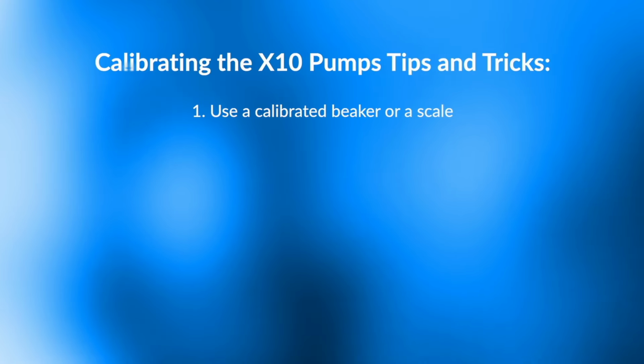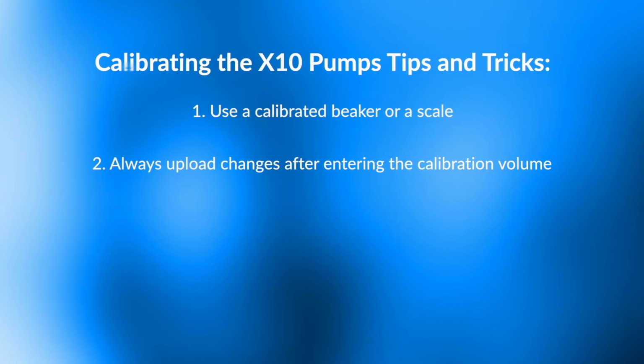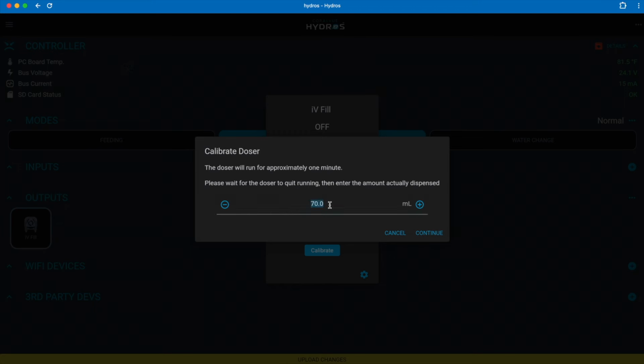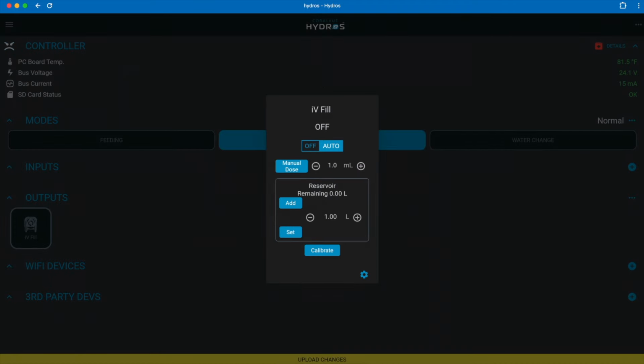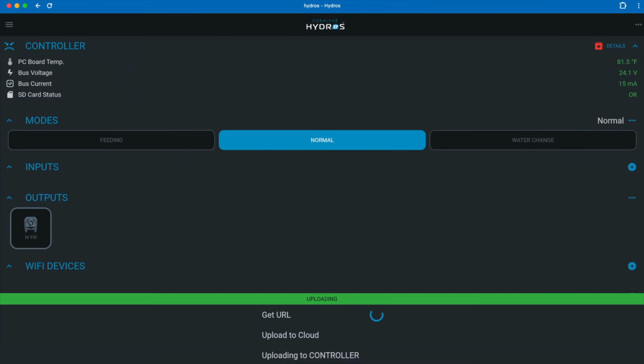Mm-hmm. All right, so what's the second tip, Dave? Yeah. So always upload changes after entering the calibration volume to ensure the calibration occurs. Always make sure you hit the calibrate button. You wait until you get the 3 milliliters or 100 milliliters, and it tells you, you read it, you type it into the app, click accept, and then upload the changes. That's the key. And after that, now you can go back to the doser and do a manual dose to verify that when I type 50 milliliters, I actually get 50 milliliters in the beaker.